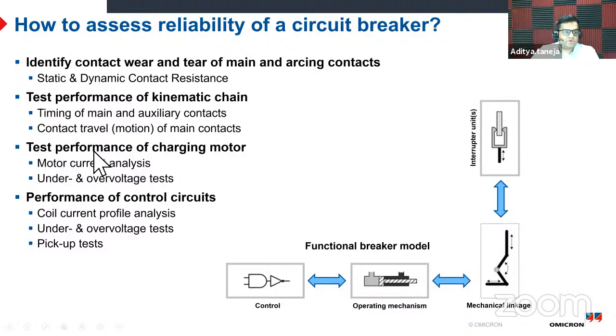Then we do the testing of the charging motor, because we have an operating mechanism there which can be different for different breakers: spring, pneumatic, hydraulic, magnetic. So many of them are there, but they are all mechanical and very specific to the vendor, and it is very difficult to check their health. Health means basically lubrication, because there are a lot of moving parts. 50 to 100 moving parts are there, which cannot be visually inspected. So what we do is we check the overall performance by analyzing the motor current.